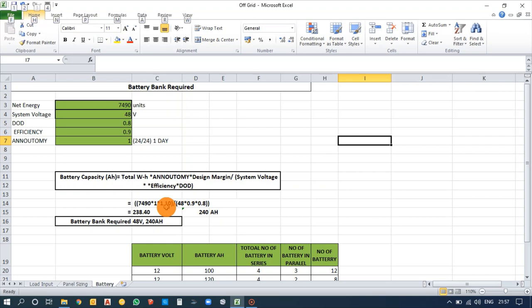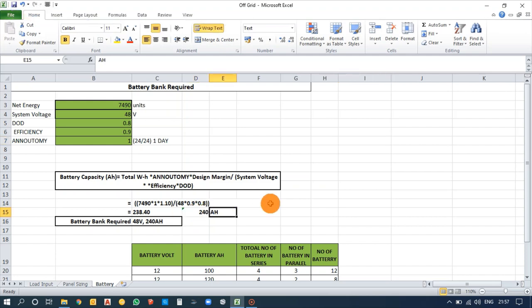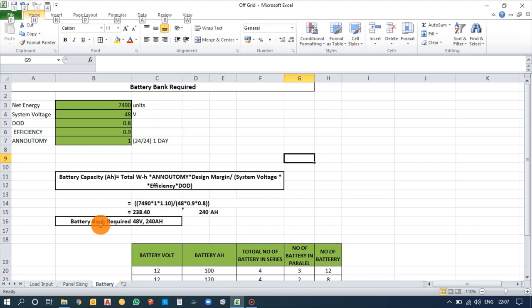Using the battery capacity formula with total watt-hours = 7,490, autonomy = 1, design margin = 1.10, system voltage = 48V, efficiency = 0.9, and DoD = 0.8, we get 238.4 Ah — rounded to 240 Ah. So the battery bank required is 48 volts with 240 Ah.